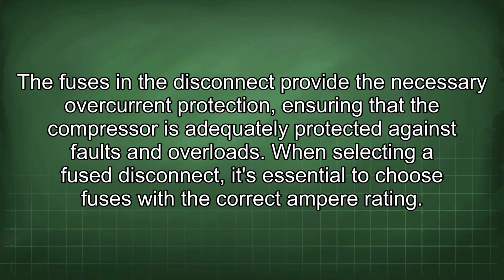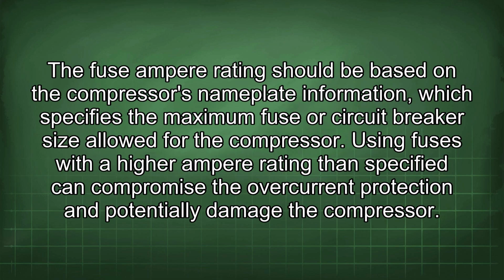The fuses in the disconnect provide the necessary overcurrent protection, ensuring that the compressor is adequately protected against faults and overloads. When selecting a fused disconnect, it's essential to choose fuses with the correct ampere rating. The fuse ampere rating should be based on the compressor's nameplate information, which specifies the maximum fuse or circuit breaker size allowed for the compressor. Using fuses with a higher ampere rating than specified can compromise the overcurrent protection and potentially damage the compressor.